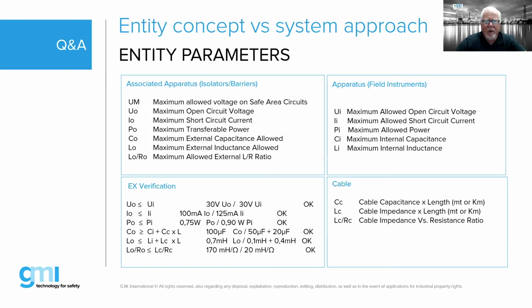For example, if we look at the first line under the Ex verification, the output has to be less than the input voltage of the device. So if our output is 30 volts and our input is 30 volts, fantastic. If our output is 32 volts, but our input max is 30 volts, then it's not okay. So we have to go through these steps to make those calculations, to validate and verify that the device is not only going to do exactly what it needs to do from an electrical standpoint, but is also safe to use. So these are the calculations that we do. I'm sorry? The cables also influence these parameters, right?